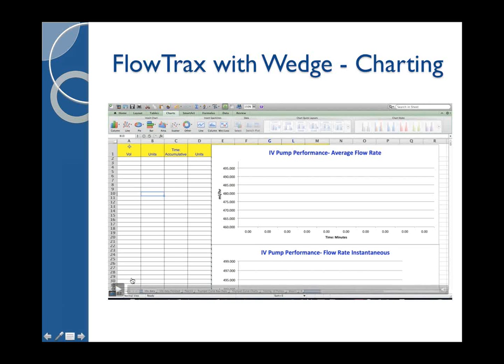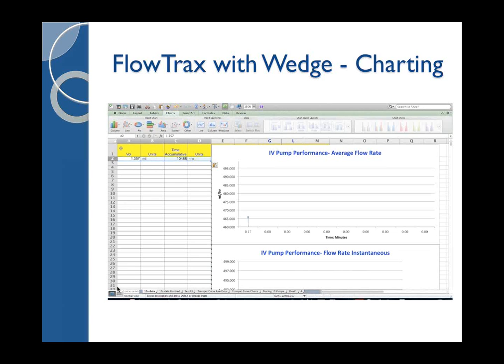In addition, we've developed what we're calling a 10-second trumpet curve capability with that Wedge program, where if you tell Trax to go into the trumpet mode, the Trax will automatically, every 10 seconds, send the data over to an Excel file, for example. And you can see here that I can chart in a microscopic way. This is sped up, of course. I didn't want everybody waiting for 10 seconds for the data to appear. You can chart in a microscopic way what's happening with the flow average over time with a particular pump.